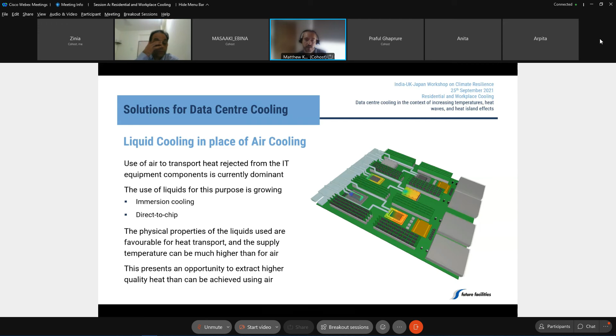The physical properties of the liquid used are favourable for heat transport, and the supply temperature of the cooling medium can be higher with liquid cooling than when using air. This presents an opportunity to extract higher quality heat for reuse, but will also make cooling easier even when the heat isn't being reused, because with liquid cooling you can typically use a higher supply temperature, making it much more viable to use liquid-to-air heat exchangers to reject heat to atmosphere as external temperature increases, helping us avoid energy intensive mechanical cooling and the associated refrigerants with high global warming potentials.